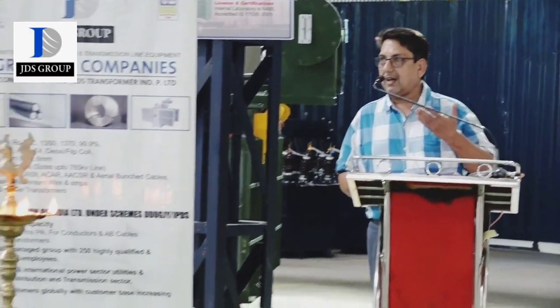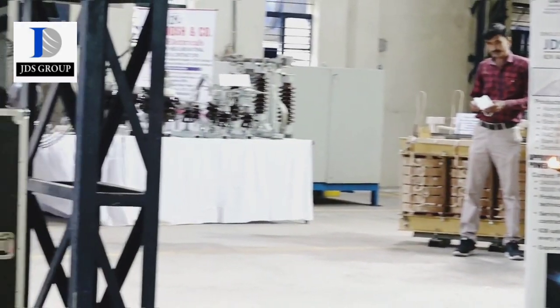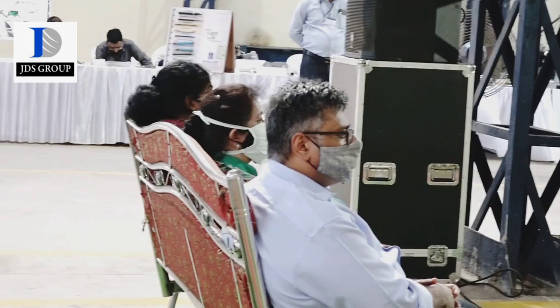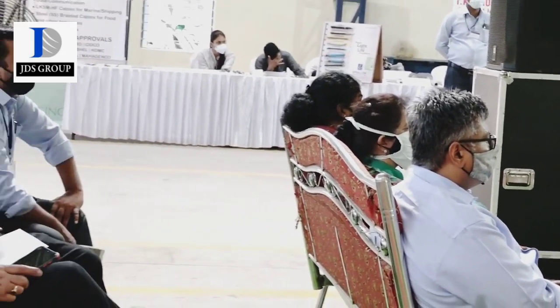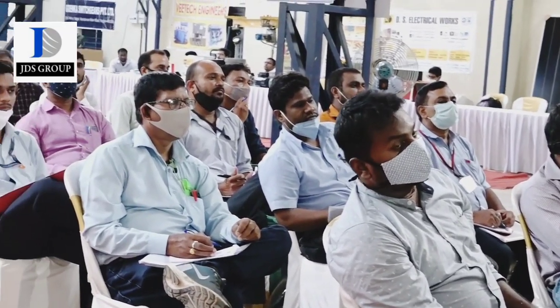Say now we are going for solar generation. The voltage generation is not linear. There is a non-linear generation of the voltage. Sometimes you get higher than 11 kV, sometimes you get lower than 11 kV. So depending on the pattern, one has to design the lightning arrester. Depending on the energy handling capacity, one has to select the lightning arrester accordingly. Okay?